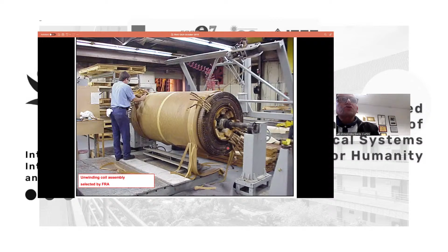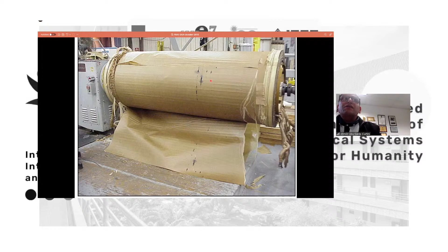Look, when we started to unwrap it, we found carbon tracking spots here, which means something happening inside. There's sustained arcing or partial discharge underneath. And when we completed unwrapping the winding, we found that the static shield of the high voltage winding was loose. That was the cause of the sustained arcing or partial discharge. The transformer looks normal and was working normal during operation. But if you leave it, you may end up having a fire. If you don't notice that something is wrong, this sustained arcing may lead to fire, a catastrophic failure.